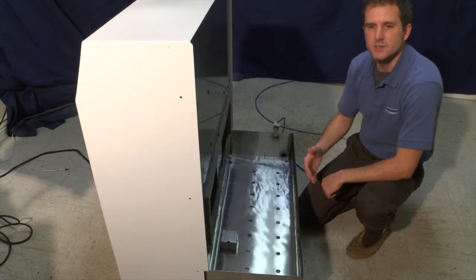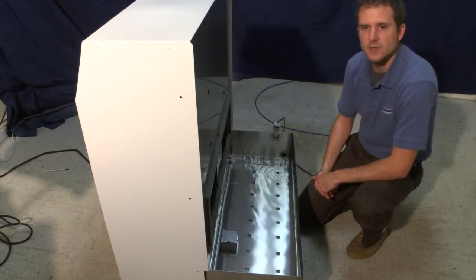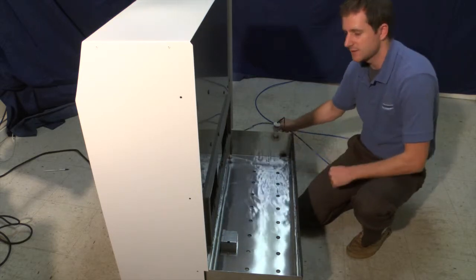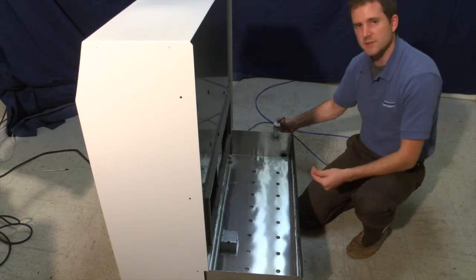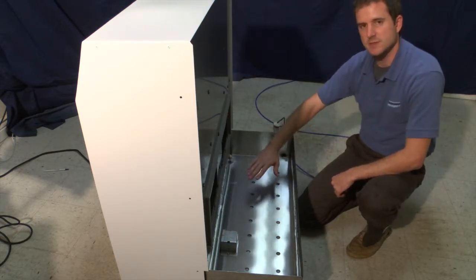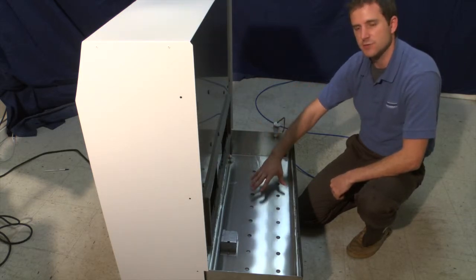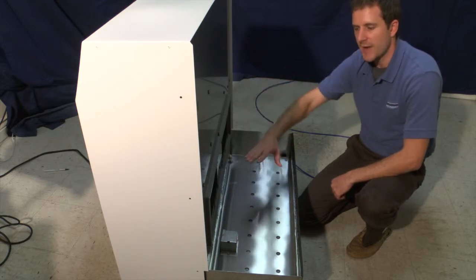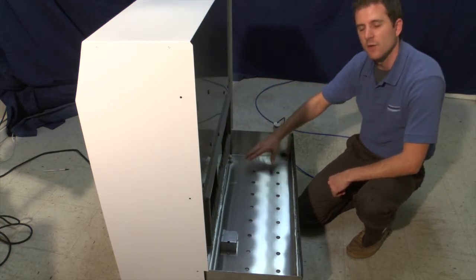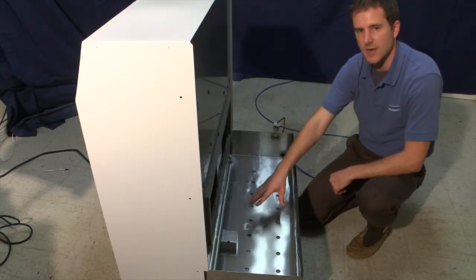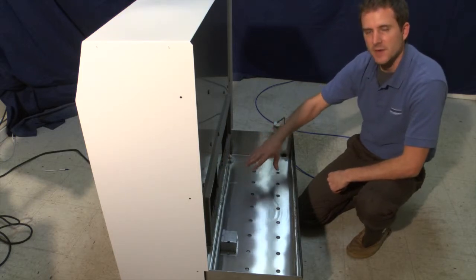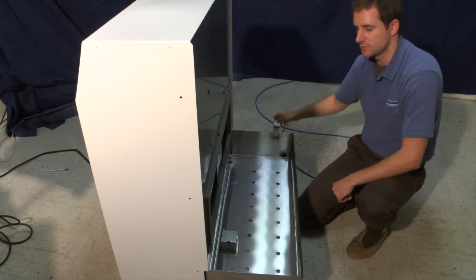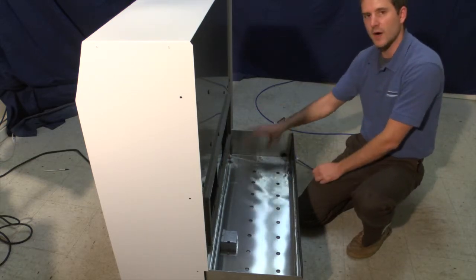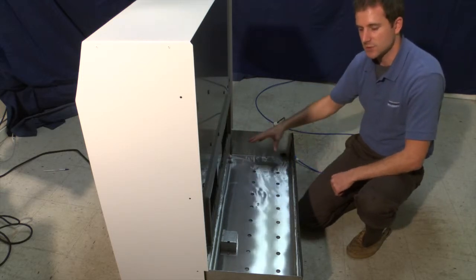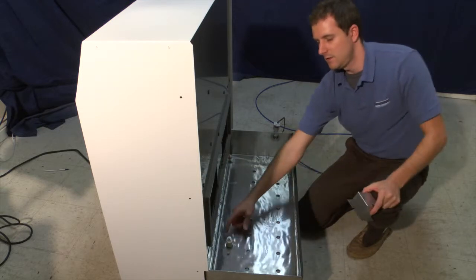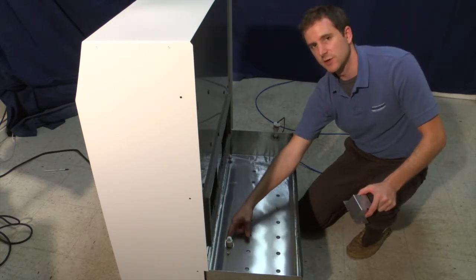In a scenario where you have an undersized RO reserve tank or undersized water treatment system that can't provide water to the humidifier fast enough, you can create a scenario where water trickles into the unit. This will sometimes allow the float to be in the position to allow the transducers to run, and sometimes not. The unit can go back and forth and chatter between operating and not operating. Or the float can reach just the level to allow the transducers to operate, but not allow it to fill up to its prime level. These scenarios can actually stress and damage transducers. You always want to make sure you have a full and proper water supply to your humidifier. And again, once the unit fills up to the proper level and the float reaches its top position, the transducers will turn back on.